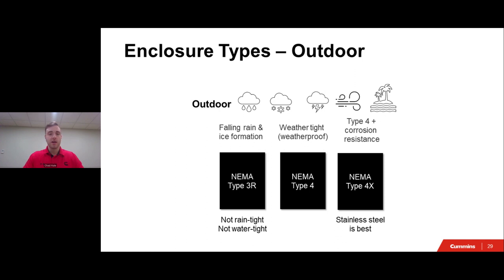So once again, brief highlight of all these. The higher you go in the system rating, so 1 to 12 for indoor, the better protection you're going to get, and same with outdoor. You have your 3R, your 4, your 4X. As you move up in those numbers, the robustness of the enclosure increases. If you are looking for more information on these enclosure types, NEMA on their website does a great job of breaking these down even more, as well as providing examples of what they look like. So you can go ahead and go to their website if you need to take a deeper look into this topic. But that's the gist of indoor and outdoor enclosures as defined by NEMA.